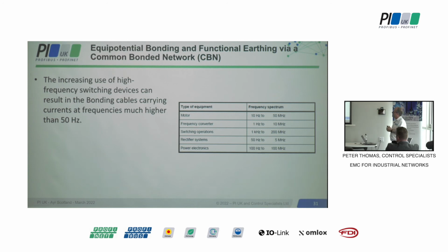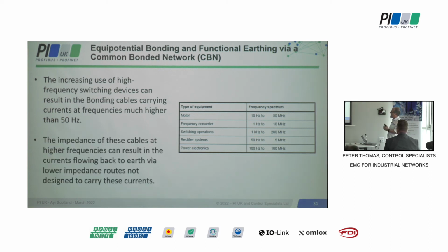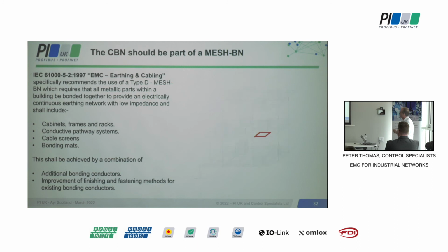So the increasing use of high-frequency switching devices can result in bonding cables carrying currents at frequencies much higher than 50 hertz. So you've now got to think that your bonding infrastructure, which is electrically safe, might not be a low impedance to these high frequency currents, and if it's not, they're going to go by whatever route they can back to their source. We will have uncontrolled flow of these currents. The impedance of these cables at higher frequencies can result in currents flowing back to the earth via a lower impedance route that is not necessarily designed for doing that.